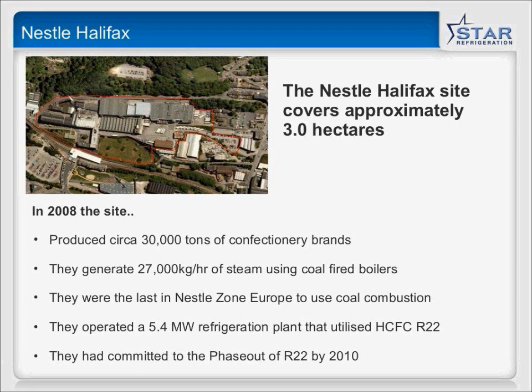Well, there's broadly two families of refrigerants - HFCs or HCFCs, pretty much the same thing, sometimes called freons, certainly synthetic refrigerants - and then there's natural refrigerants. It's almost impossible to go from one to the other with the same kit. Ammonia doesn't mix well with copper, which tends to be the material of choice in HFC installations, so if you're looking to change from HFCs to ammonia, pretty much tough luck. There are some other refrigerants popping up that can sometimes be a drop-in for R22, but they're still of the same family. For example, the ISCEON range of refrigerants from R22 are lower ozone depleting, which gets you out of one challenge. So it's possible to do that.